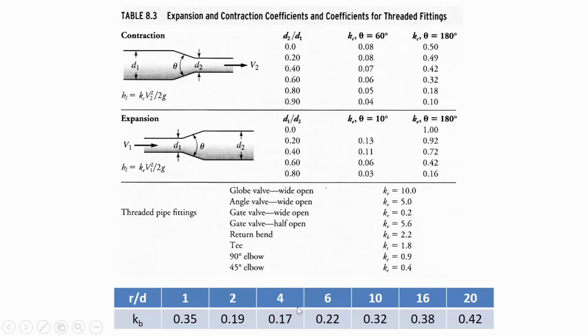And you may remember, talked about in a pipe bend how the more gradual the transition, the lower the energy loss is, up to a point where the radius of curvature relative to the diameter of the pipe, the sweet spot seems to be a ratio of about 4, because that's the lowest K value. That's going to have the least amount of disturbance.